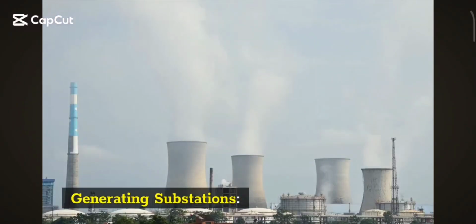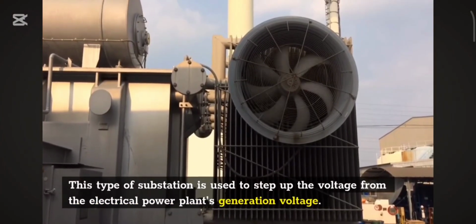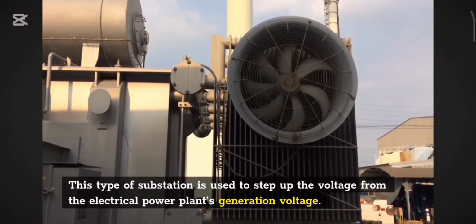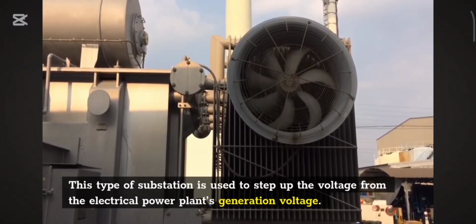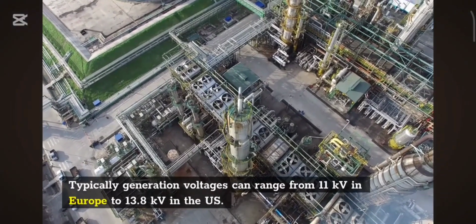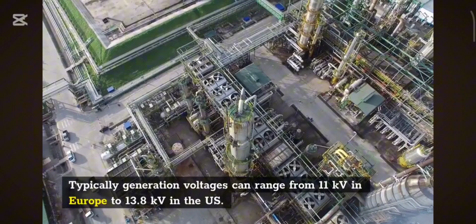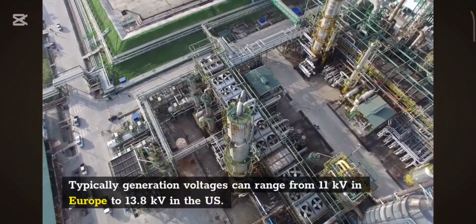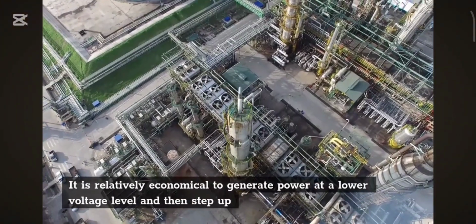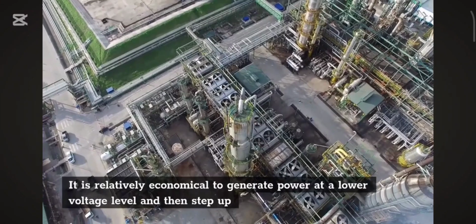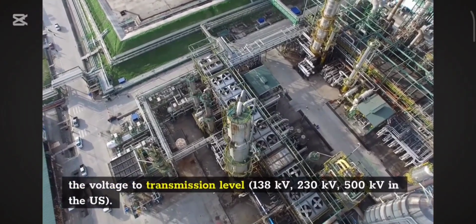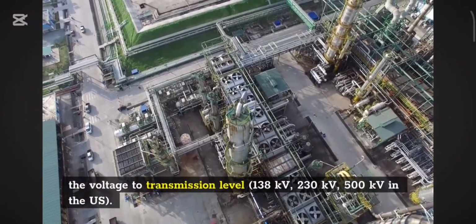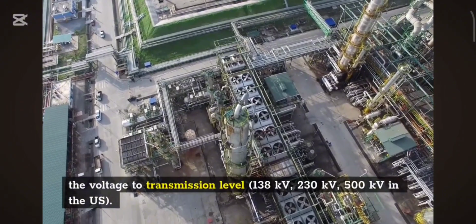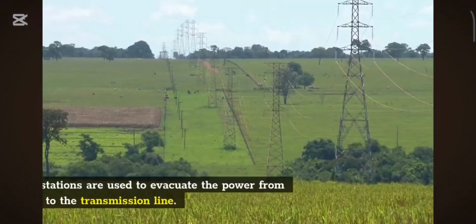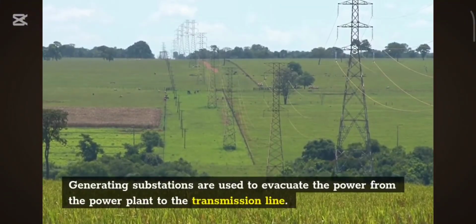Substations. This type of substation is used to step up the voltage from the electrical power plant's generation voltage. Typically, generation voltages can range from 11 kV in Europe to 13.8 kV in the US. It is relatively economical to generate power at a lower voltage level and then step up the voltage to transmission level, 138 kV, 230 kV, 500 kV in the US. Generating substations are used to evacuate the power from the power plant to the transmission line.